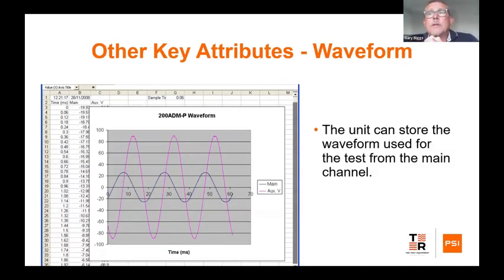Another key attribute with our test sets, which again is unusual for these heavier power relay test sets, or as they're commonly known, SCITs, secondary current injection test sets, is we have the capability of storing the output waveform. Now, when you look at a specification of a relay, it's taking it for granted that that relay will be fed with a sine wave. If the relay isn't fed with a sine wave, it's not going to react and meet the manufacturer's specifications.